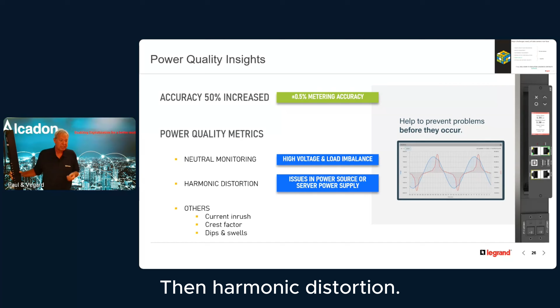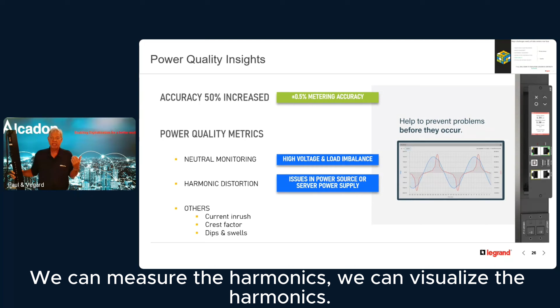Then harmonic distortion is actually a reflection caused by connecting a server, destroying your sine wave. If I connect just 1 computer to my power infrastructure, my sine wave gets disturbed just a little bit. As you see in the picture, we can visualize the sine wave also. If I'm connecting more computers, the disturbance of my sine wave gets bigger and bigger and bigger, to a certain point where my power quality is simply not reliable anymore. We can measure the harmonics, we can visualize the harmonics, so we can see how good or how bad the quality of your power is. We can see how much your sine wave gets damaged.